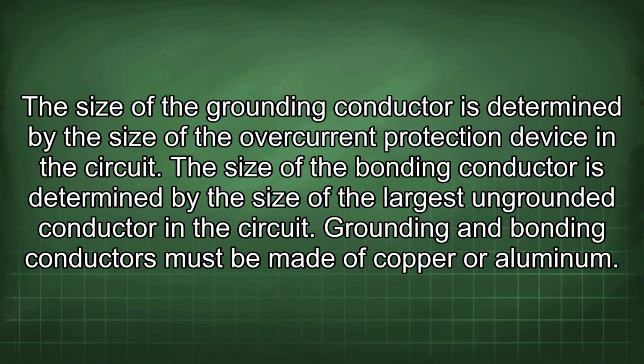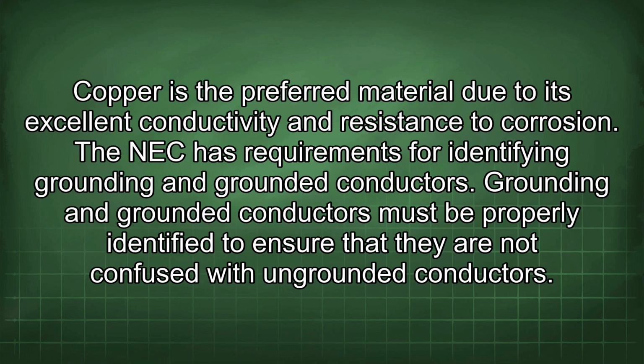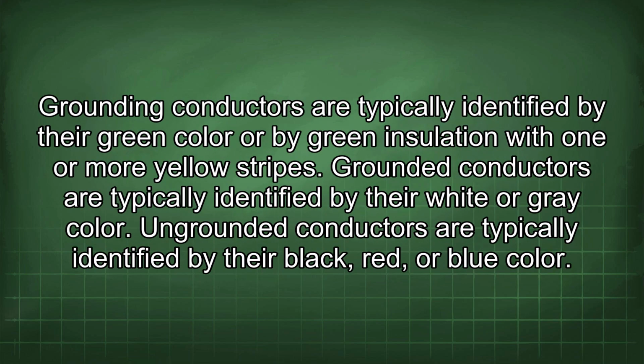Grounding and bonding conductors must be made of copper or aluminum. Copper is the preferred material due to its excellent conductivity and resistance to corrosion. The NEC has requirements for identifying grounding and grounded conductors. Grounding and grounded conductors must be properly identified to ensure that they are not confused with ungrounded conductors. Grounding conductors are typically identified by their green color or by green insulation with one or more yellow stripes. Grounded conductors are typically identified by their white or gray color. Ungrounded conductors are typically identified by their black, red, or blue color.